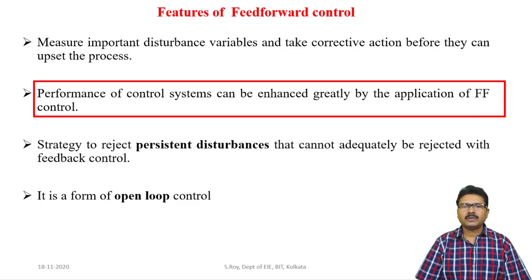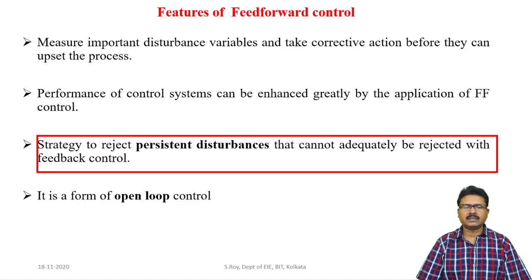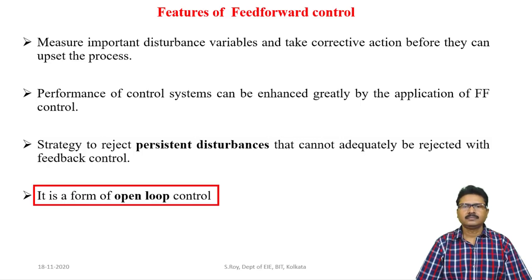If we use feedforward control along with other systems, the performance can be enhanced greatly. Feedforward control is a strategy to reject persistent disturbances that cannot be adequately rejected using only a feedback control system. Feedforward control is a form of open-loop system — there is no feedback signal, and all signals flow in the forward direction.